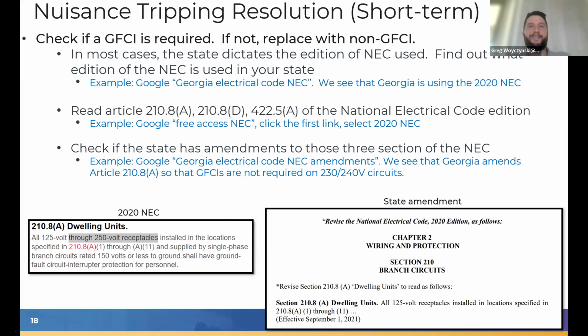So in most cases, the state dictates the edition of the NEC used. So step one, find out which edition of the NEC is used in your state. And I'm going to use Georgia as an example. So I can just Google Georgia Electrical Code NEC. And we get a Georgia government link. I forget if it's the first or second link. We click on it. We see that Georgia is using the 2020 NEC. Then we can read these 3 paragraphs. They're short, in layman's terms: 210.8A, 210.8D, and 422.5A of the National Electrical Code edition. So I can Google free access NEC.